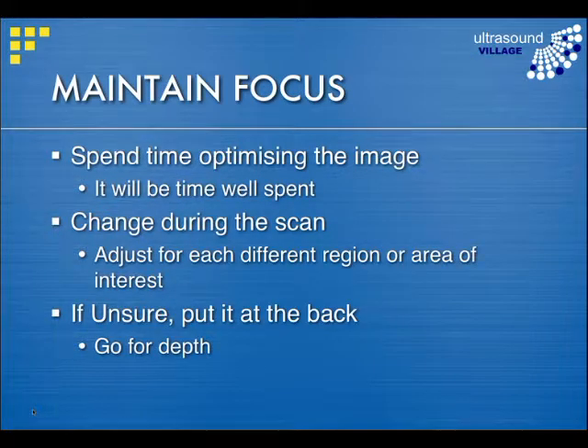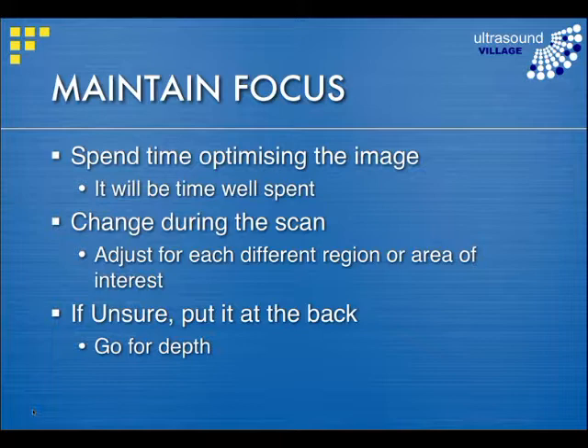Many machines have a moveable focus, though not all — some do this automatically. If you have a machine with an adjustable focus, take time to move it to your point of interest or just slightly below. Because you'll be looking at different things through the scan or at the same thing from a different angle, you'll need to keep adjusting this. If you're unsure where your area of interest is, generally having your focus towards the back of the image is better than having it too superficial.